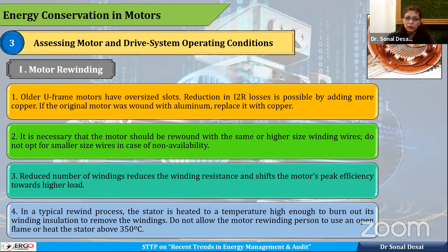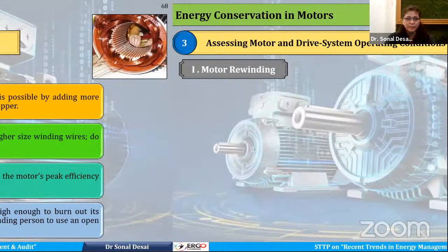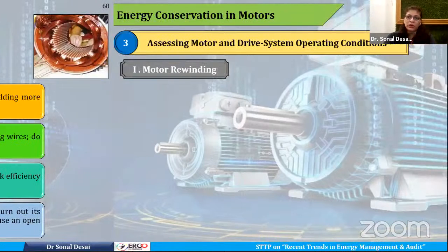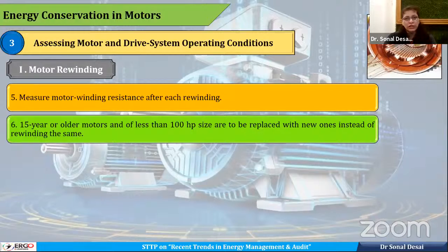And to remove the older winding, normally a labor person will heat up the motor to remove the insulation, but make sure that in any case that temperature does not increase beyond 350 degrees centigrade, otherwise it will damage the motor. So make it operate at lower than 350 degrees centigrade. Then whenever we are doing the rewinding process, always measure the resistance after each and every rewinding. If the motor is 15 years old and less than 100 HP size, it is always good to replace the motor rather than rewinding it.